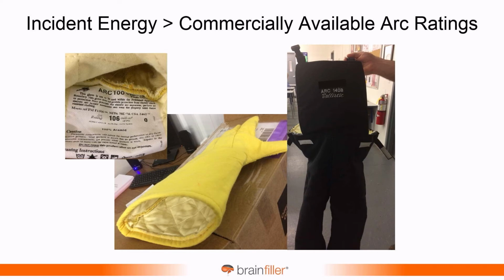First off, I want to mention PPE. The arc ratings have been going up considerably. This one on the right, that's actually my hand holding it up. It almost stood up by itself. This is an arc rating of 140 calories. And so arc ratings continue to increase, but not everybody has access to this kind of PPE, and you can still have incident energy levels above these values.